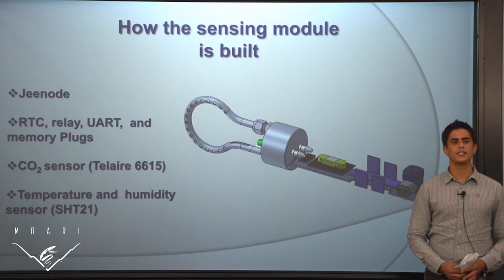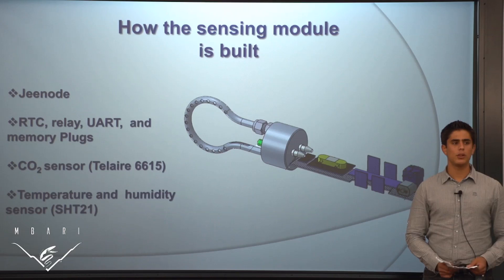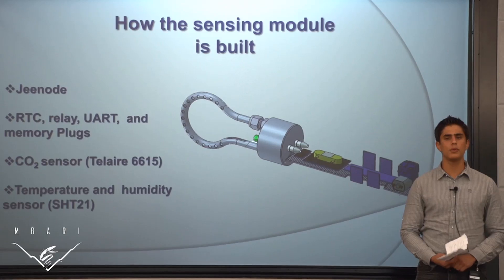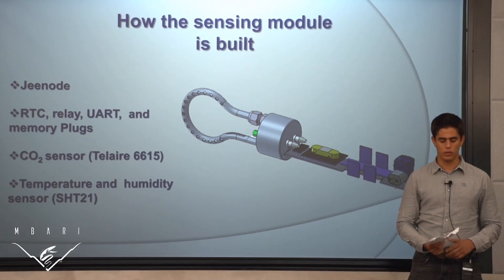It works by using the Teflon AF tubing to equilibrate the PCO2 that is in the water into the tubing system on the sensor. It also works with the Telaire 6615, which is our CO2 sensor. It's a flow-through sensor which communicates using the UART protocol.